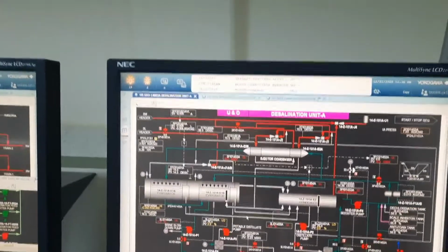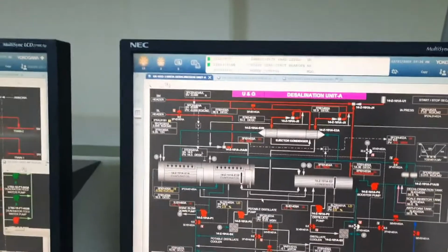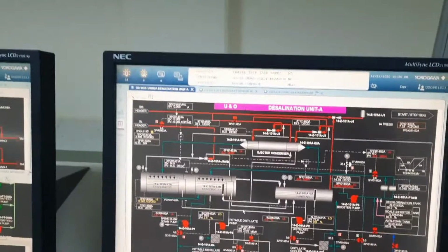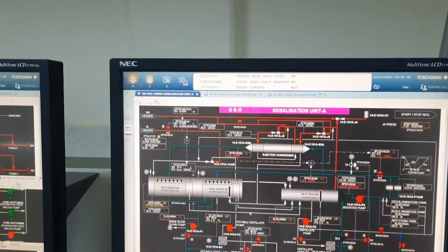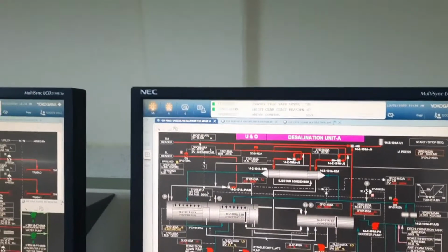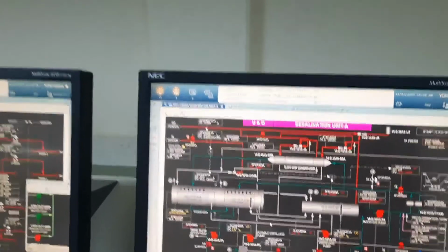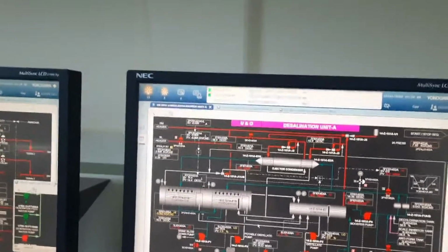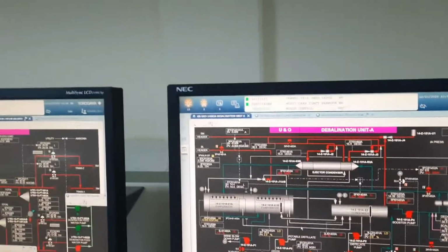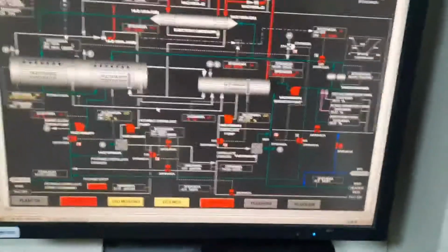If at that time the water color at the sampling side changes, turning blue or purple, you must immediately stop the acid cleaning without asking anyone. So when they take a sample, they also need to check the water color, whether it is changing or not. If it is changing, we understand that the calcium carbonate is probably already removed, and the attack has started on the tube bundle. Okay, so this is the main function.